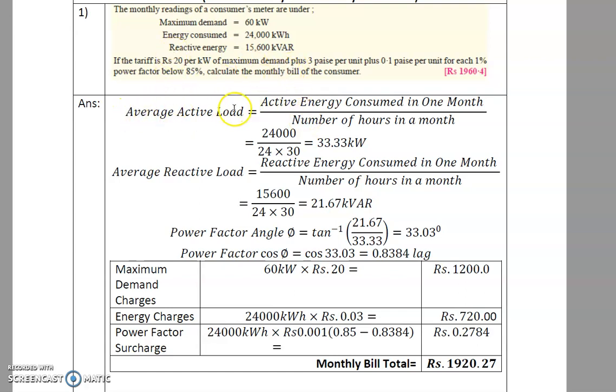First, it is necessary to calculate the power factor. We calculate the average active load: active energy consumed in one month divided by number of hours in a month — 24000 kWh divided by 24 hours into 30 days — which gives 33.33 kW. Similarly, average reactive load is 15600 divided by 24 into 30, giving 21.67 kVAr.